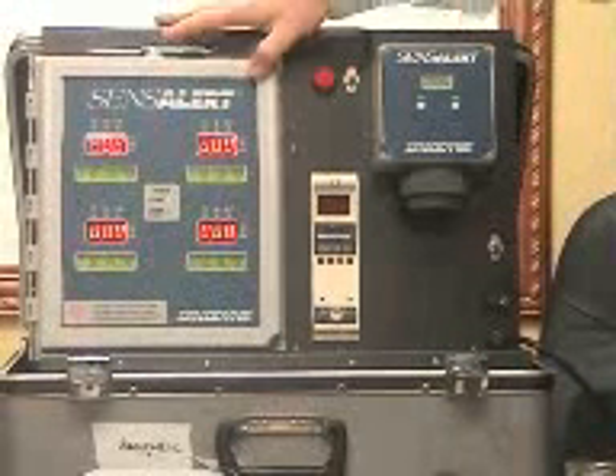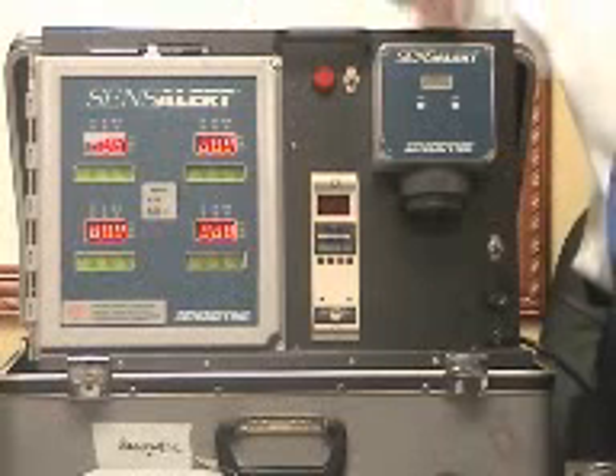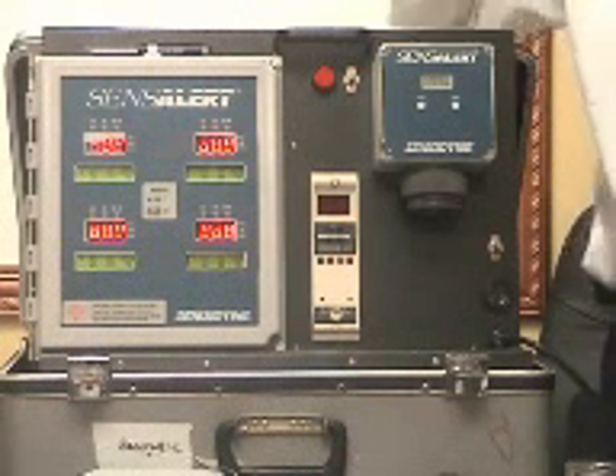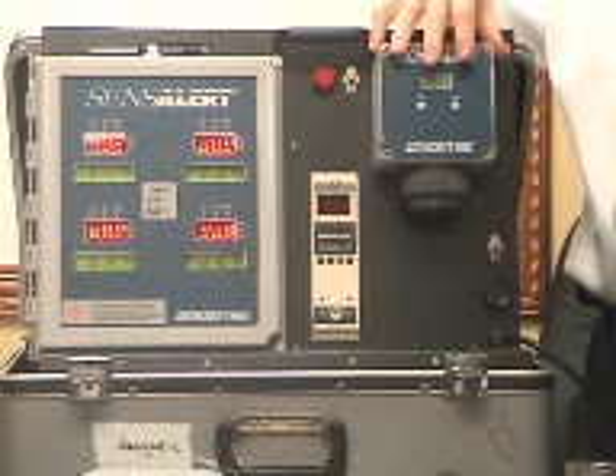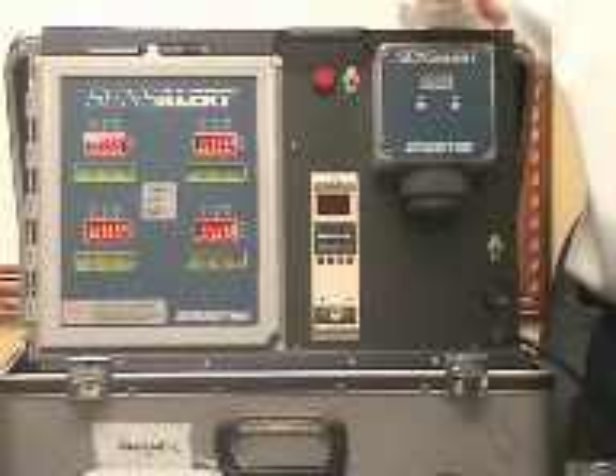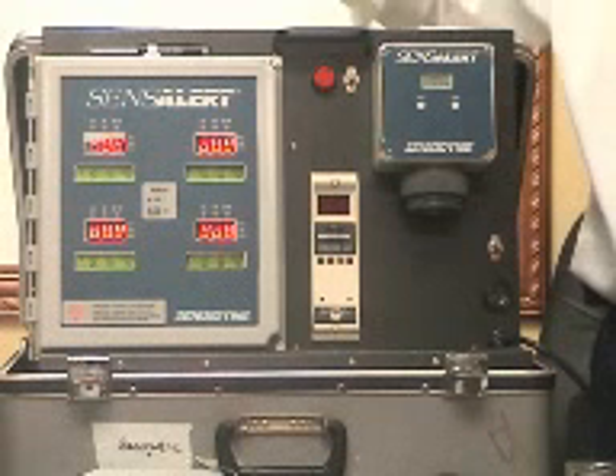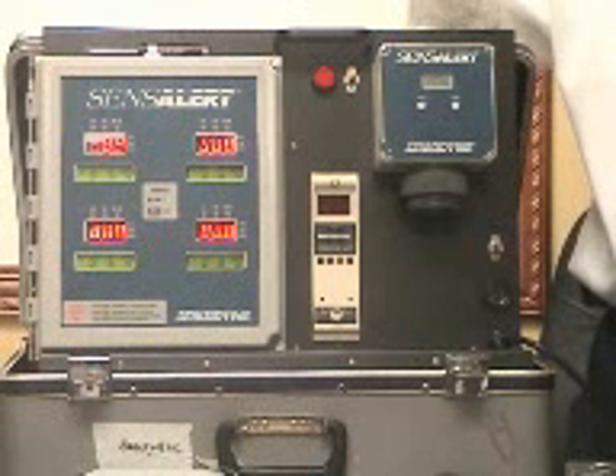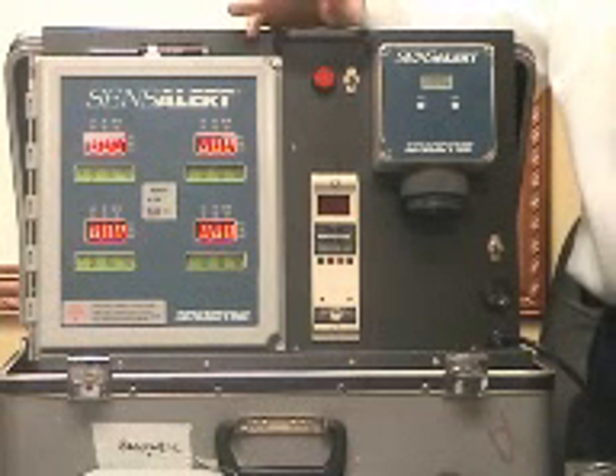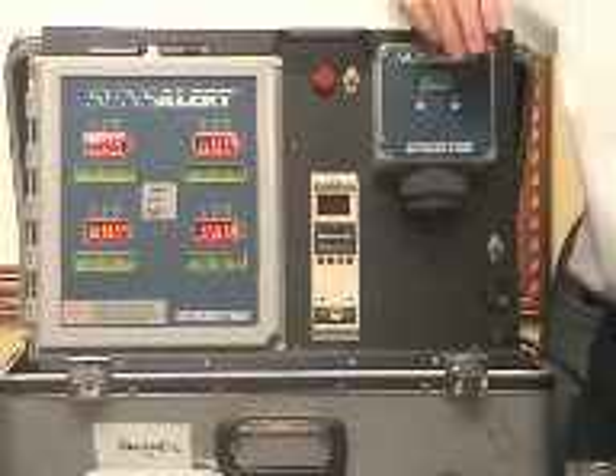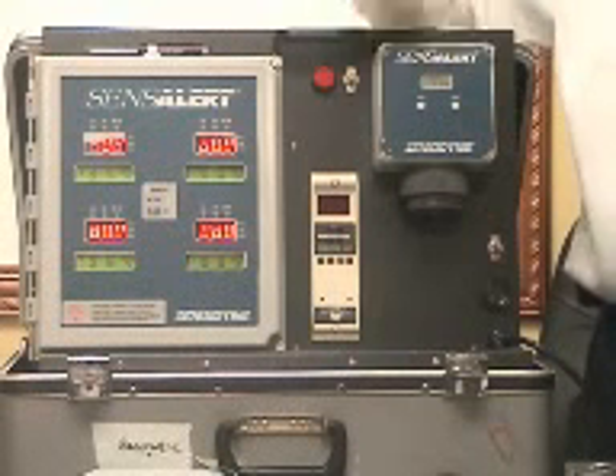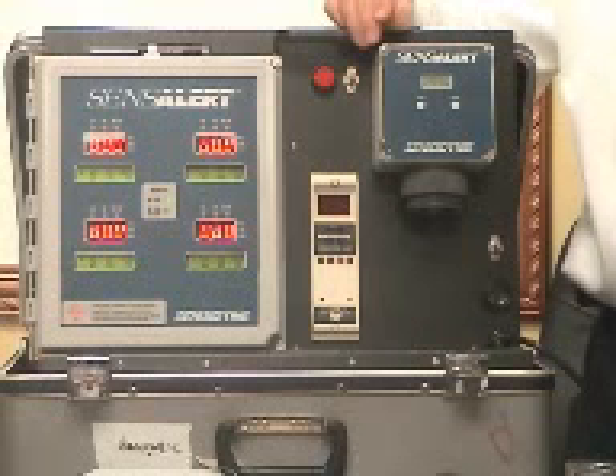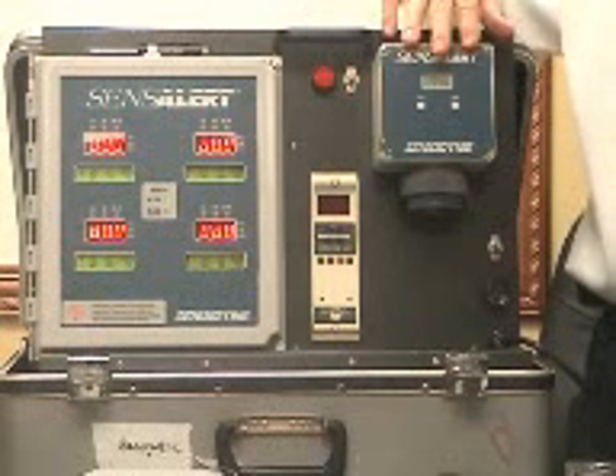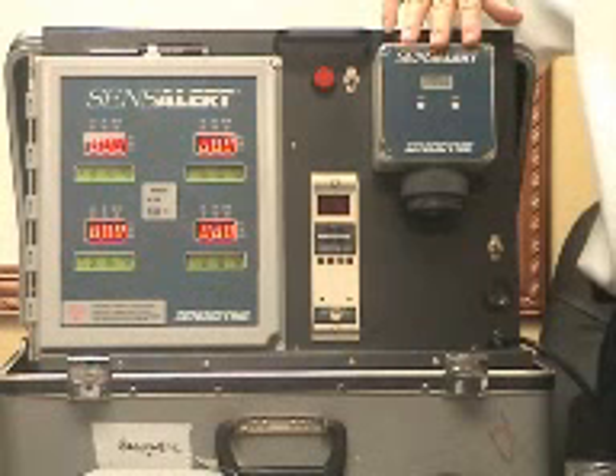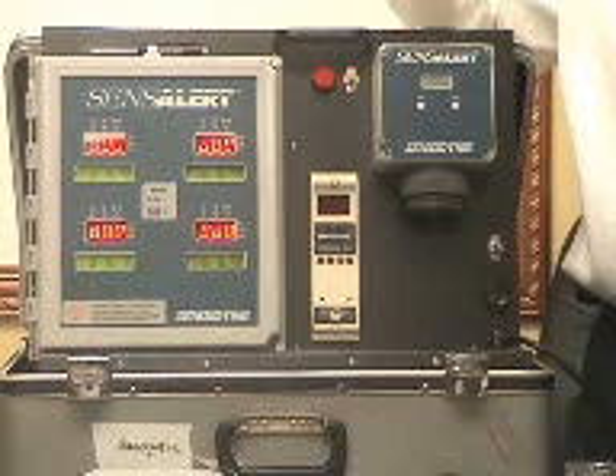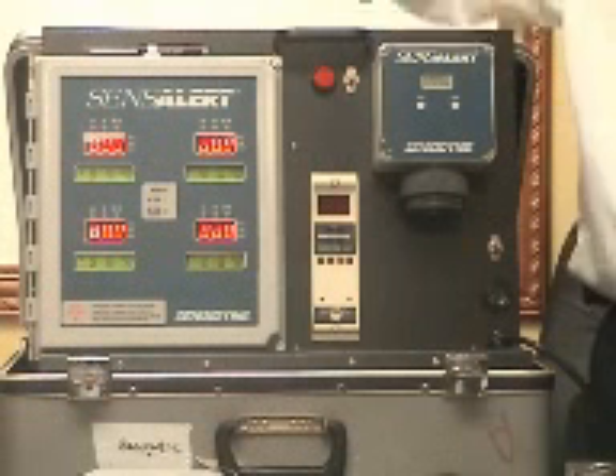So that's the 4-channel controller and the transmitter. Again, one universal transmitter for the several gas types in the facility, and the benefit is that they don't need to have so many spare parts to support all their gas needs. A lot of people say, quote me 3 chlorines, 2 combustible transmitters, and 2 ammonias, and spare parts for 1 year. So all you do is quote them the 3 transmitters for ammonia, 3 transmitters for combustible, 3 for chlorine, and 1 transmitter for spare part for all of them.